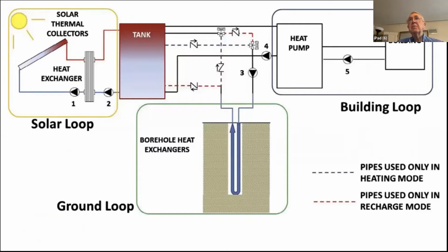Anyway, here's another example of a multi-source heat pump. And this was a design done by people in Italy. And in this case, there's no air source mode at all, but instead the multi-source comes about from a solar thermal collector. And if you attended the first talk in this session today, you would have learned a little bit about solar thermal collection. So that's at the upper left here. And the solar heat feeds into a buffer water tank. And then there's a heat pump for a building. And again, you see a number of water pumps. And the other symbols there with the letter Z or whatever, those are special types of one-way valves. But anyway, there are borehole heat exchangers.